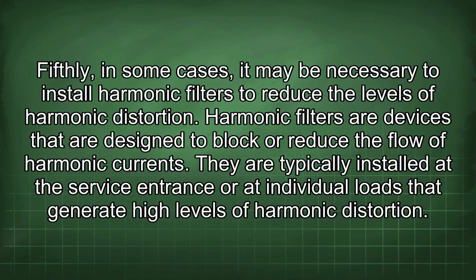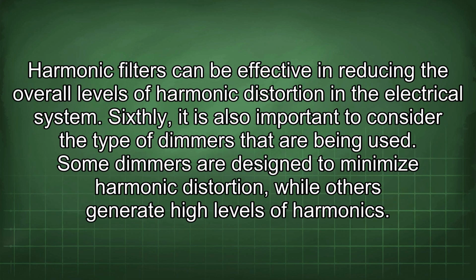Fifthly, in some cases, it may be necessary to install harmonic filters to reduce the levels of harmonic distortion. Harmonic filters are devices that are designed to block or reduce the flow of harmonic currents. They are typically installed at the service entrance or at individual loads that generate high levels of harmonic distortion. Harmonic filters can be effective in reducing the overall levels of harmonic distortion in the electrical system.